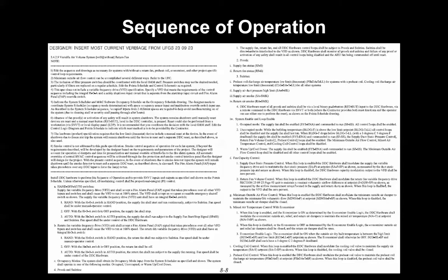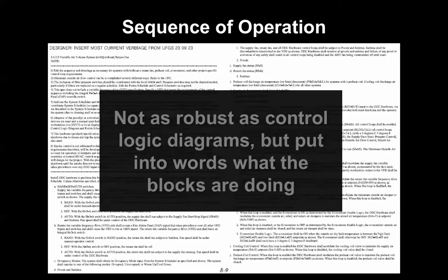So you may have the sequence of operation in this narrative form here, and this works best when you're supplementing the control logic blocks, not necessarily replacing them. Because a controls programmer would have to take these words, fill in some blanks, or use their own judgment to build control logic blocks in the programmable controllers. So it's handy to have both, but where you have the sequence of operation, it's nice to be able to have this plain words way of communicating what these systems should do.